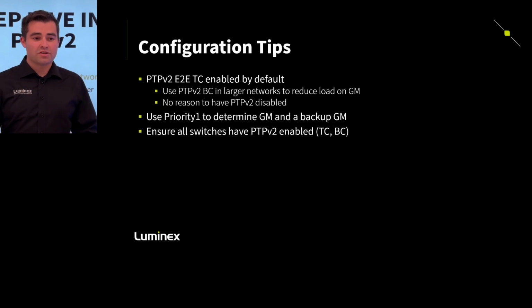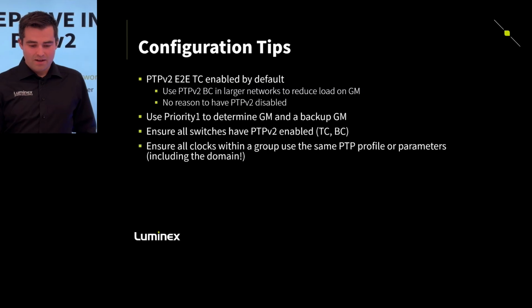Ensure that all switches in your network have PTPv2 enabled or are PTPv2 capable. This can be transparent clock or boundary clock mode. And ensure that all devices in your network, all clocks within the group, have this exact same set of parameters, so the same profile. This includes the domain value as well. It has to be the same, otherwise the devices cannot sync to each other.